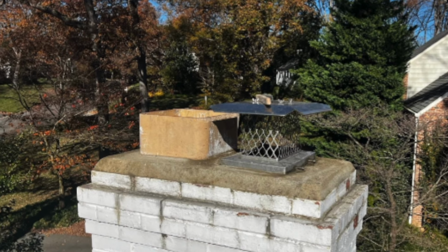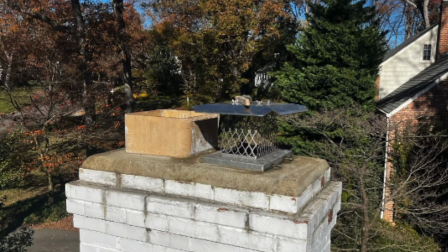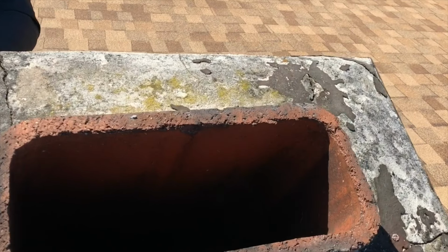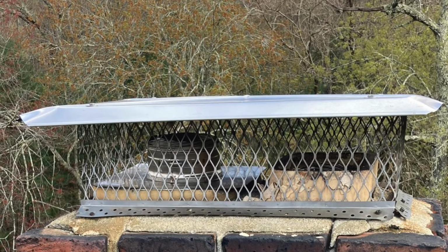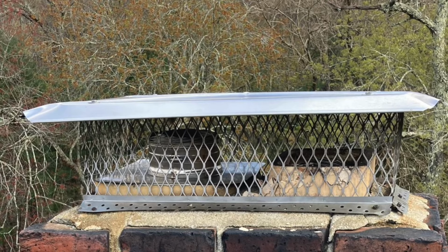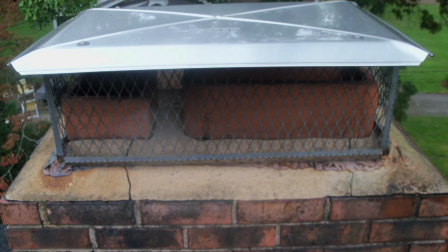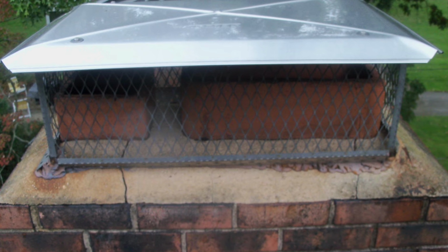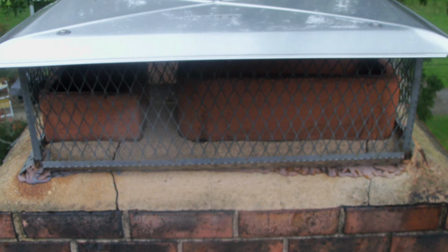In addition, chimney caps are required to be removable at the top to allow for proper inspection and cleaning of the flue, as a permanently affixed cap would interfere with maintenance and cleaning procedures. NFPA 211 also provides specific guidance for multi-flue chimney caps. According to Section 4.62, the minimum vertical distance from the underside of an unlisted multi-flue chimney cap to the top of the flue it covers must be equal to the lesser dimension of the flue's opening.